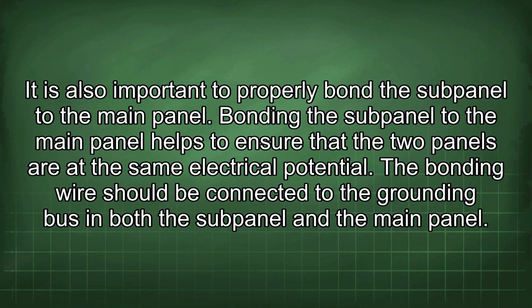It is also important to properly bond the subpanel to the main panel. Bonding the subpanel to the main panel helps to ensure that the two panels are at the same electrical potential. The bonding wire should be connected to the grounding bus in both the subpanel and the main panel.